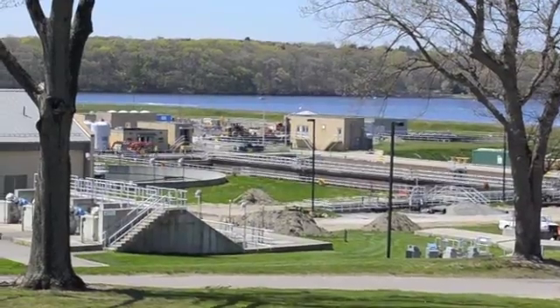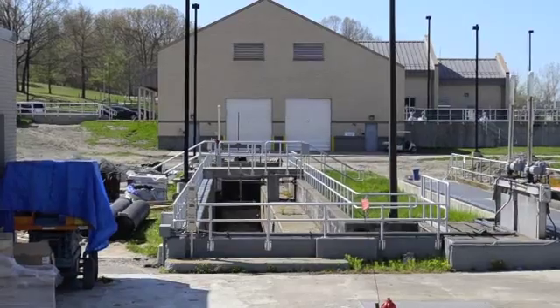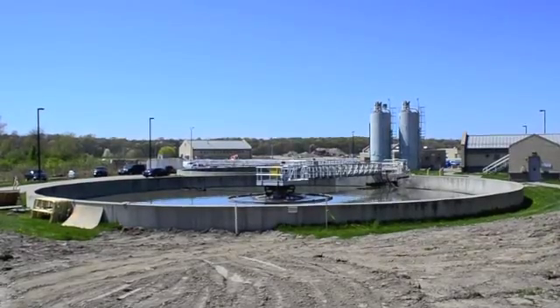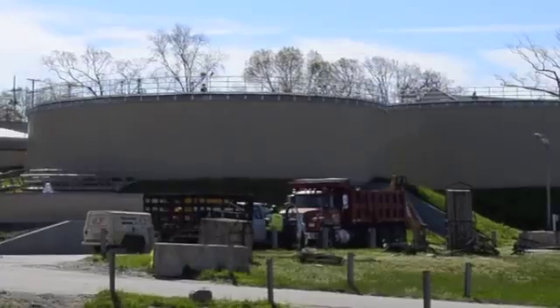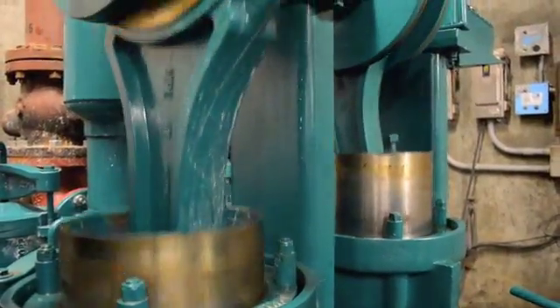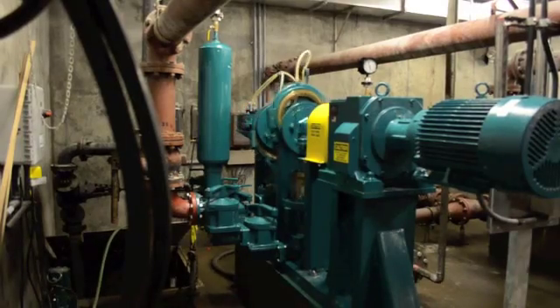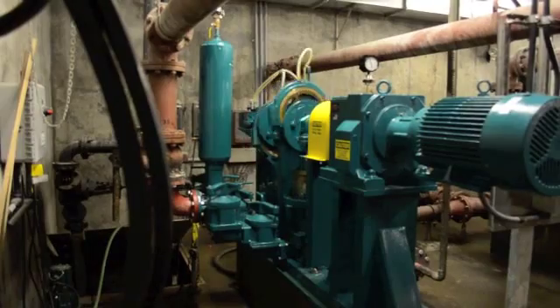The conditions at the facility call for pumps to transfer thickened, waste-activated sludge containing at least 5% solids from storage tanks and facilities digesters. The pumps are expected to transfer sludge up to 197 gallons per minute at a maximum of 160 feet of total discharge head.